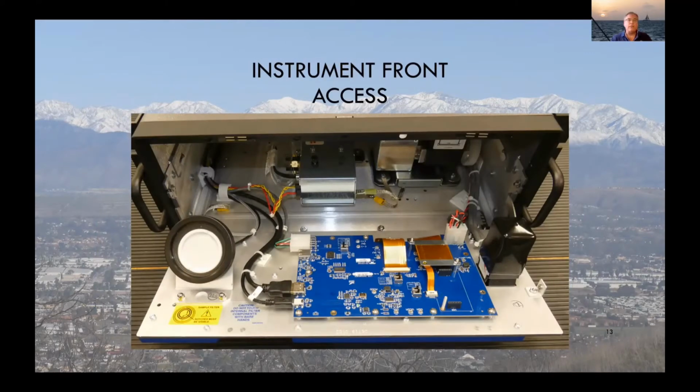This is once again the front of the instrument with the access port pulled open. As you can see, you can view the inlet filter. It's very convenient right there. You can see it through the glass top to tell whether or not it's dirty and needs to be cleaned. These generally need to be replaced, depending on conditions, about once a week. We have display boards and such here.